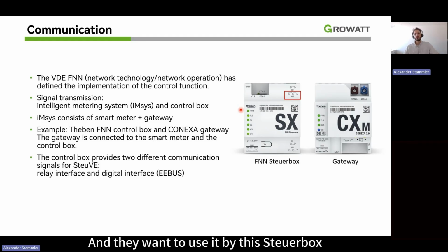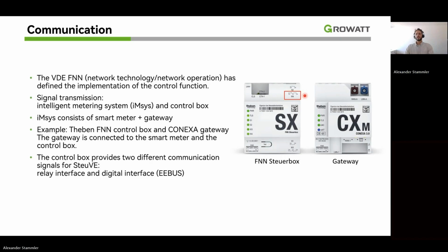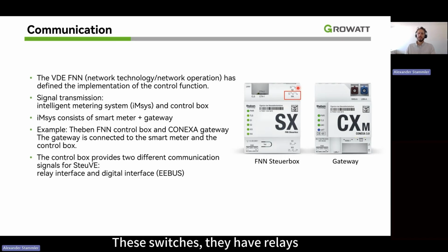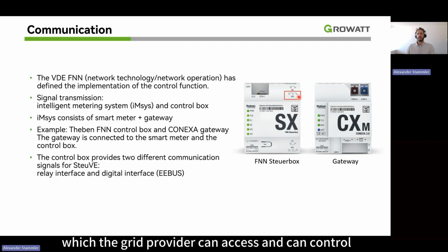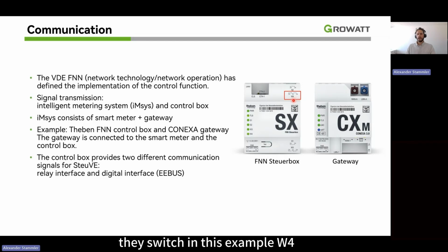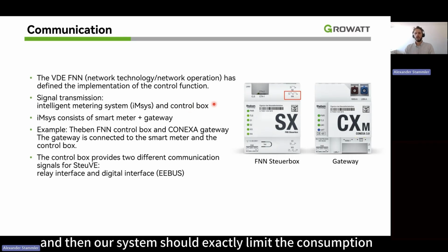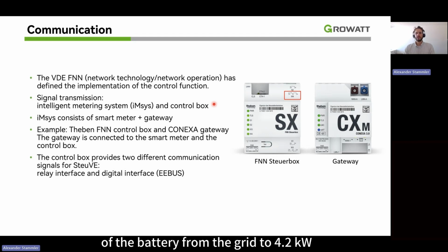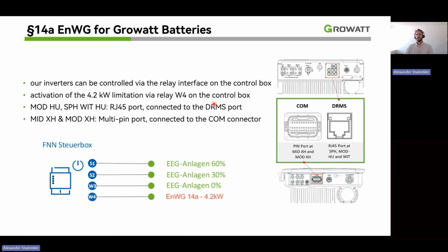And they want to do it by exactly this Steuerbox or Rundsteuerempfänger. So we use all these switches. They have relays which the grid provider can access and can control. So if they say now we have the bottleneck, they switch, in this example W4, the relay of W4, and then our system should exactly limit the consumption of the battery from the grid to 4.2 kilowatt. This is exactly limited to EV chargers because they can consume more than 4.2, and it's our batteries which can also consume more than 4.2 kilowatts.